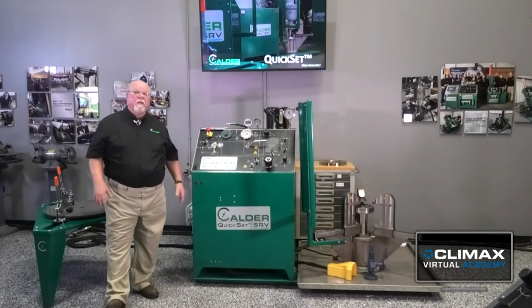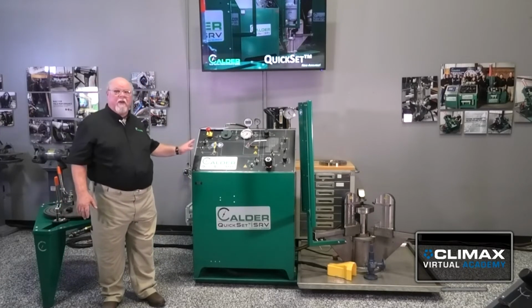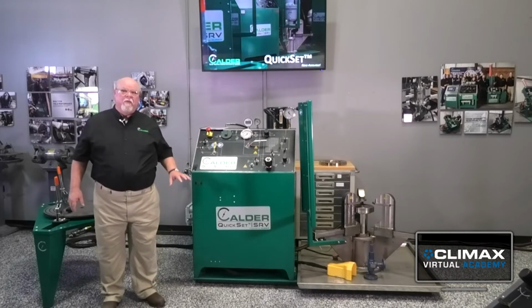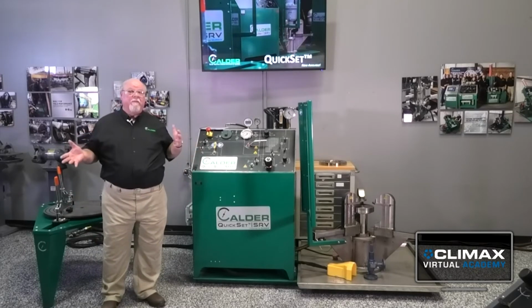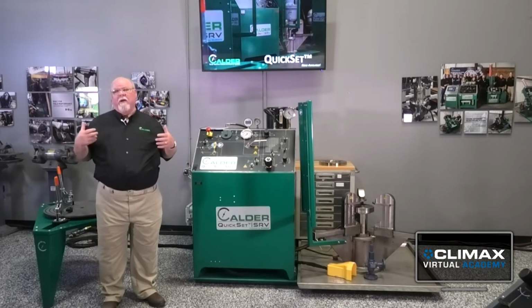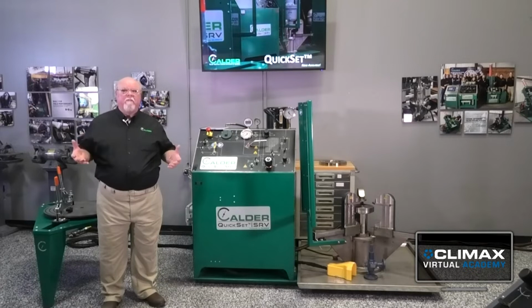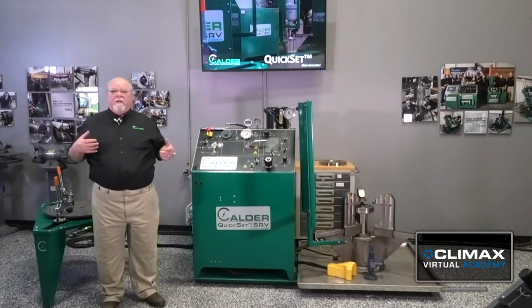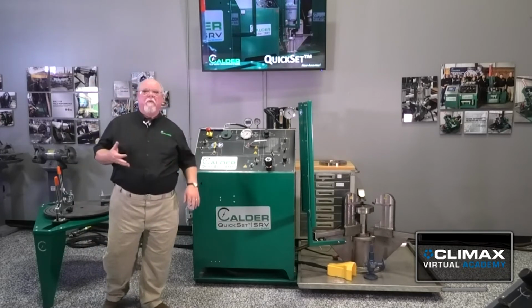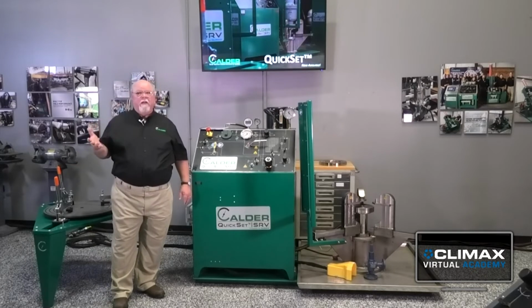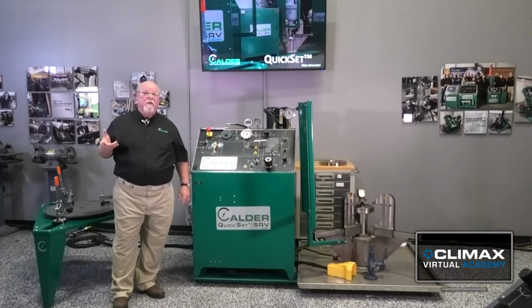The other part of the field upgradable is the test vessel size and the seal plate inlet size as well. We start off standard with a 1 gallon vessel and a 3/4 inch feed. And we can upgrade to a 2.5 or 5 gallon vessel and a 1 inch feed as well. So again, the standard base configuration is 30 ton up to 10 inch valves, testing 6,000 PSI gas with a 1 gallon vessel and a 3/4 inlet connection. Then we can go on up to a 60-ton clamp for up to 16-inch valves. They can test up to 6,000 PSI gas, 2.5 gallon vessel and a 1-inch inlet. So we have 4 different combinations in those ranges. That's a min and a max, so you can size based on your application.